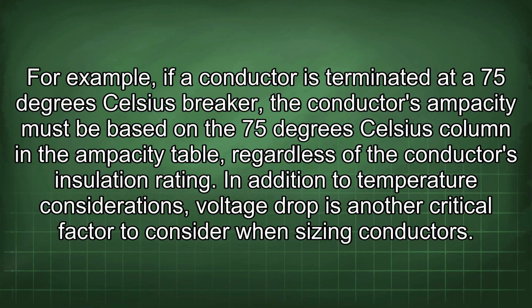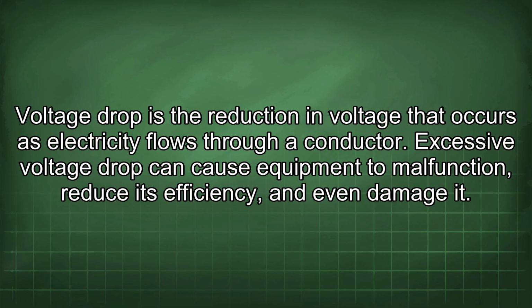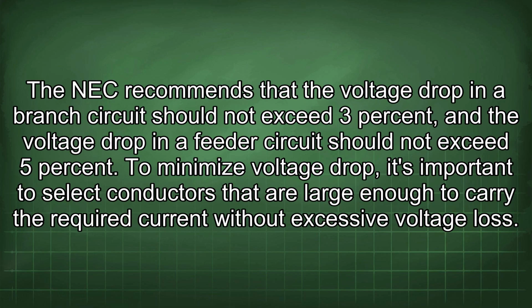In addition to temperature considerations, voltage drop is another critical factor to consider when sizing conductors. Voltage drop is the reduction in voltage that occurs as electricity flows through a conductor. Excessive voltage drop can cause equipment to malfunction, reduce its efficiency, and even damage it. The NEC recommends that the voltage drop in a branch circuit should not exceed 3%, and the voltage drop in a feeder circuit should not exceed 5%.